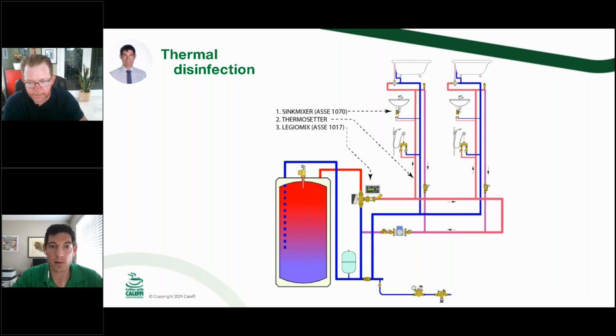And every week you've got a data logged, verified thermal disinfection cycle that is a legal asset for you too, to say nothing left this mechanical room above this temperature, and also we disinfected at this date to this temperature. We verified that we've taken it out of the comfort zone for legionella, and this is all data logged for 30 days. That can be a very important thing to have on your side, to make sure that you can prove that you're doing your job well, and something that is generally very hard to say, that no, this valve did not scald anybody.